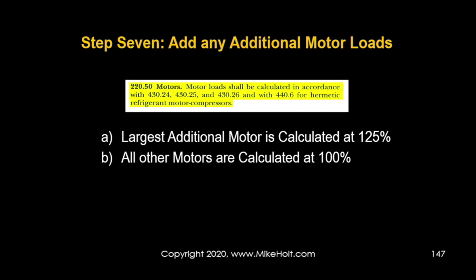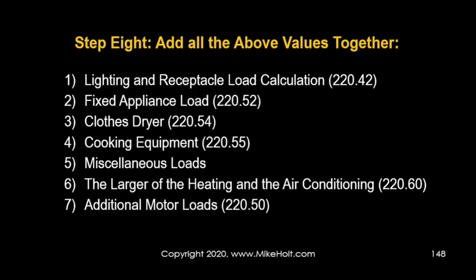Step 7: add any additional motor loads — at 125% for the largest motor, 100% for all others. Step 8: add everything together — lighting and receptacle load (derated), fixed appliance load, clothes dryer, cooking equipment, miscellaneous loads, the larger of heating or A/C, and additional motor loads. Most examples will omit steps 5 and 7, effectively working through steps 1, 2, 3, 4, and 6.